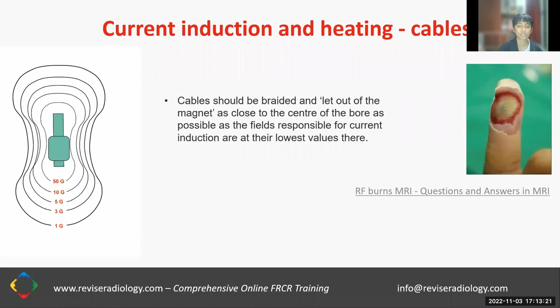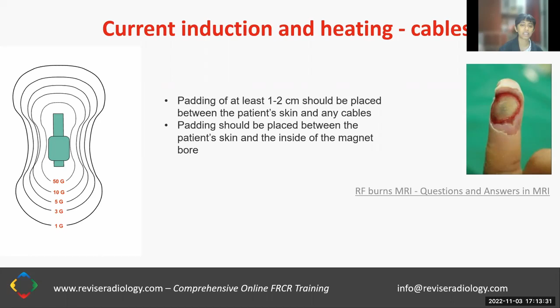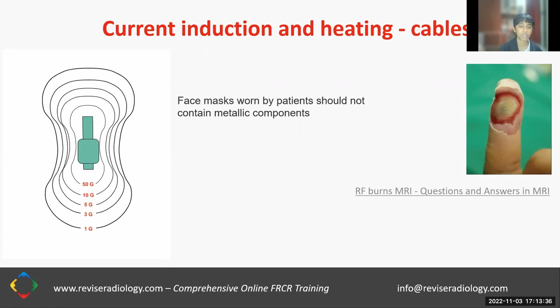A padding of at least 1 to 2 centimeters should be placed between the patient's skin and any cables. The padding should be placed between the patient's skin and the inside of the magnet bore. Face masks worn by patients should not contain metallic components.